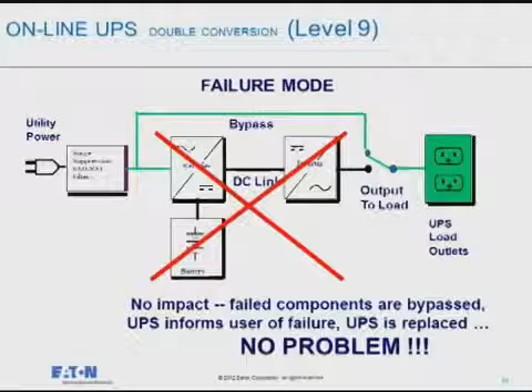And the other nice or critical design feature of an online UPS is the fact that because you're always using the components, if there is a failure, you immediately know of the failure. The UPS will transfer to bypass and isolate the power components and notify you of the failure. And here's where it gives you, as an operator or the business unit, the opportunity to make the decision. Yes, my load is fully exposed to all power anomalies on the utility. I can choose to either turn off the loads or I can choose to run them in this manner.